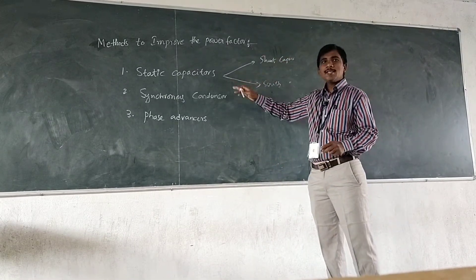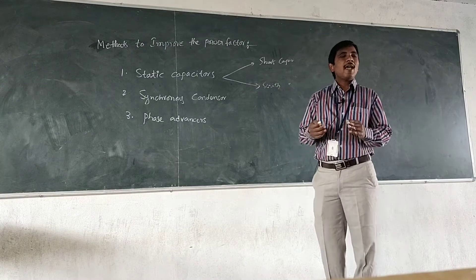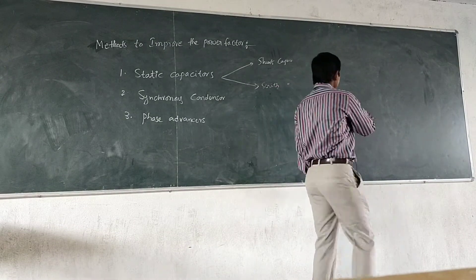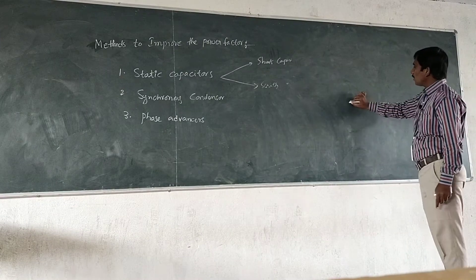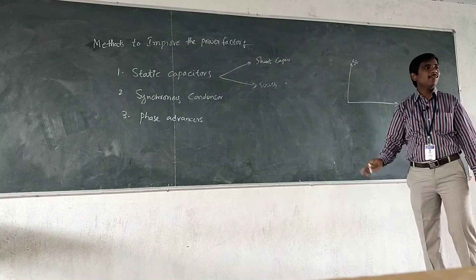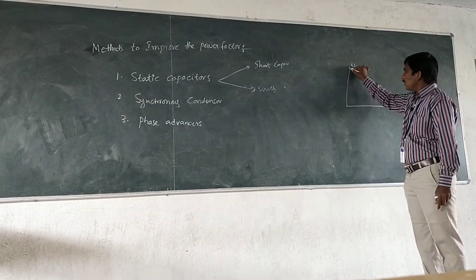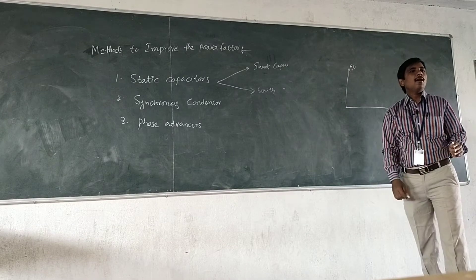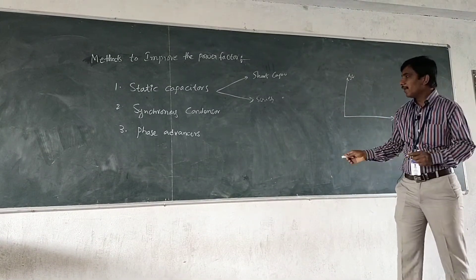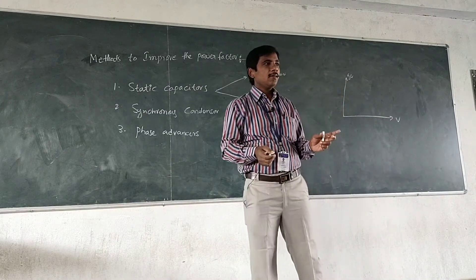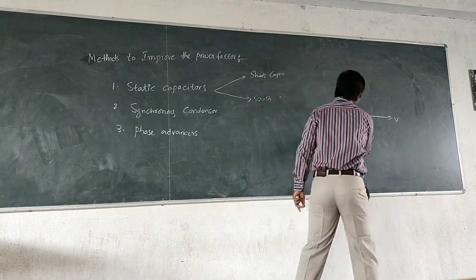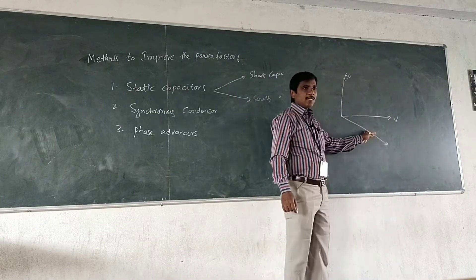These static capacitors improve the power factor. Actually, capacitors take the leading current. Suppose the voltage is applied — the capacitor takes the leading current. The capacitor current will always lead the supply voltage. This leading current neutralizes the lagging component of load current. Induction motors are the main cause for low power factor in industries, as induction motors take lagging current.